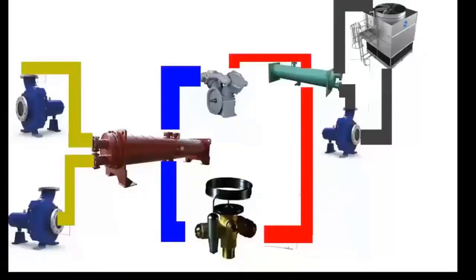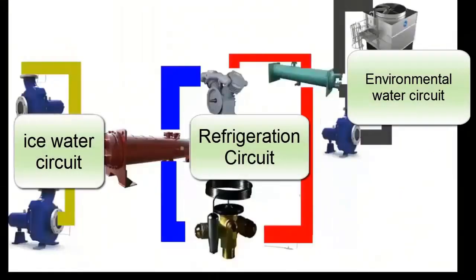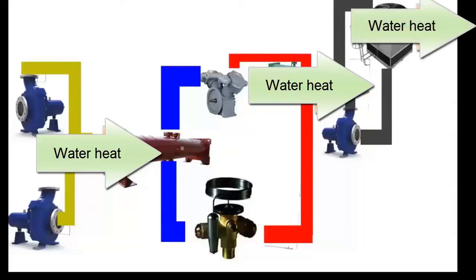In this class we aimed to show that there are chillers whose condensers are cooled by water, giving us three circuits that never communicate as fluids — only thermal communication through heat exchange. On the left: an ice water circuit. In the center: a refrigeration circuit. On the right: an ambient water circuit that cools the condenser, with a cooling tower and a condensation pump. The heat flows from the water to the refrigerant in the cooler, then the refrigerant carries that heat to the condenser, delivers it to the ambient-temperature water, which then goes to the cooling tower and delivers it to the air.